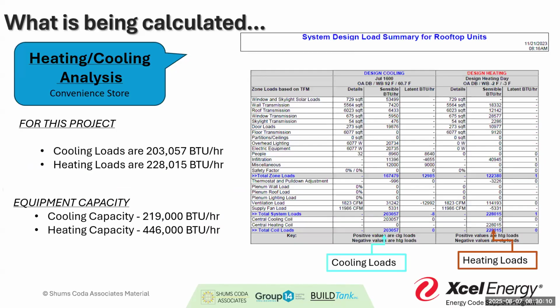But again, I take that load, all those individual elements, I add them together. I can see that I've got enough capacity to meet the load demand. And like I said, we're seeing here this 446,000 BTU of heating is almost double what we're going to need to meet the load requirements of the building. Especially if I'm building this in a Roswell, a Clovis, or a Hobbs, I'm probably not going to need that much overage. And again, that's where the code is coming in future editions to say wait a minute, you oversized too much - that's how we determine when you've oversized too much.